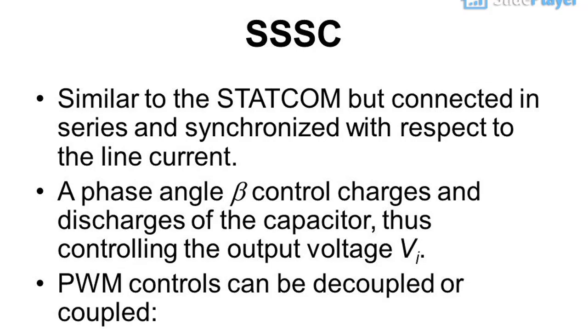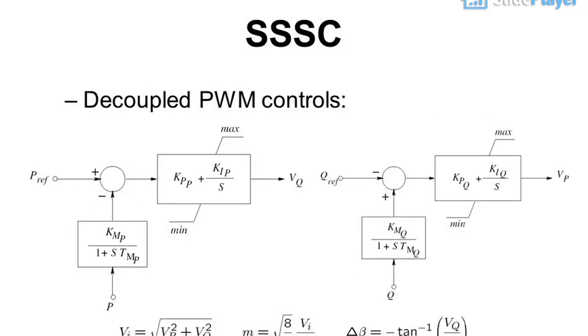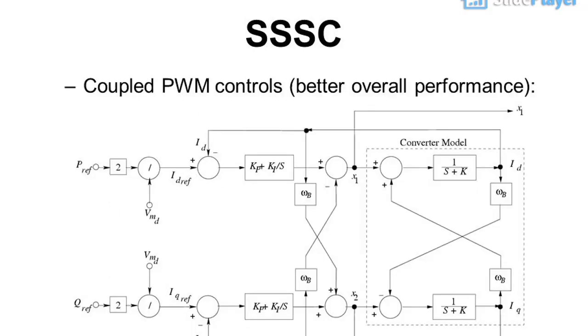SSSC: similar to the STATCOM but connected in series and synchronized with respect to the line current. A phase angle control charges and discharges the capacitor, thus controlling the output voltage. PWM controls can be decoupled or coupled; coupled PWM controls yield better overall performance.